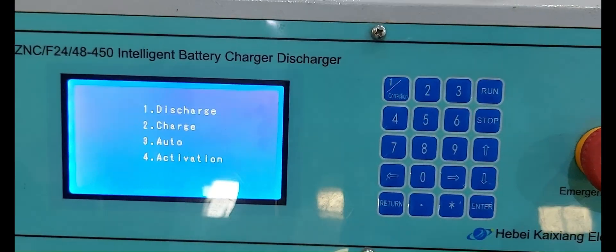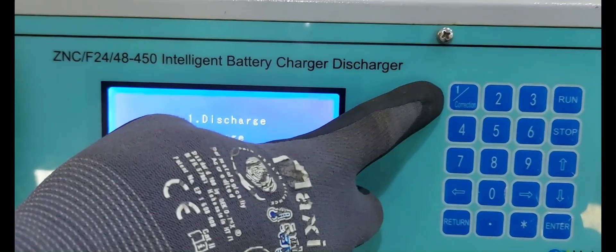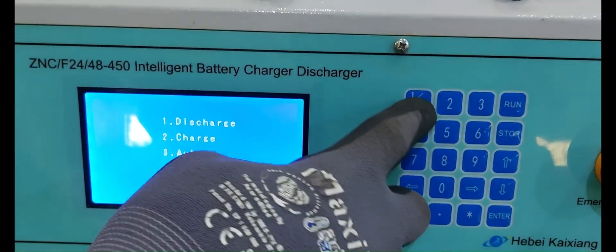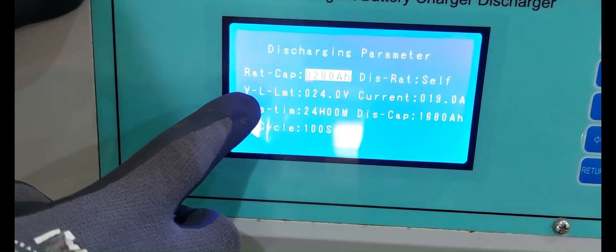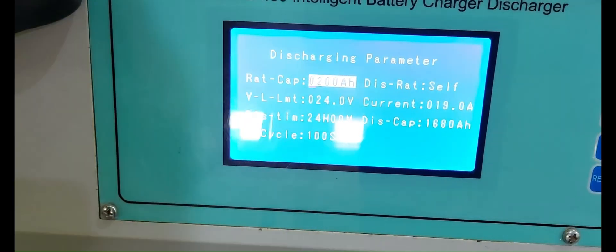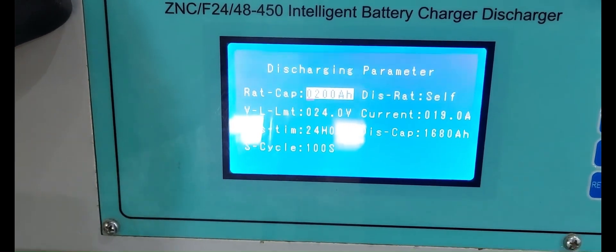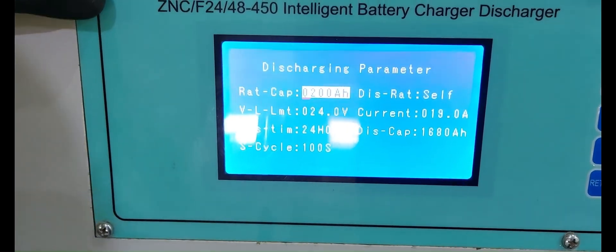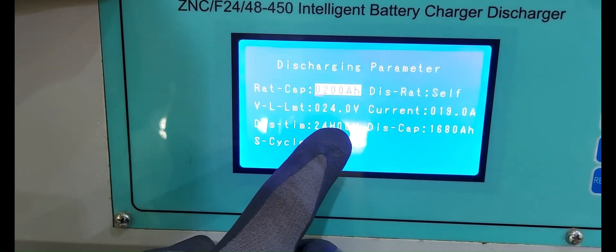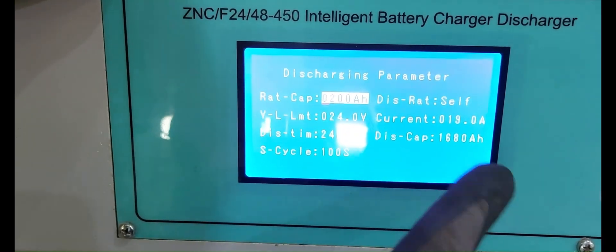Next, we are doing the discharge parameters — the discharge scenario. First, check the discharge capacity — rated capacity of 200 Ah. Discharge ratio: self. Voltage limit low limit: 24 volts. Current: 19 amps. Discharge time: 24 hours. Discharge capacity: 1680 amp-hours. Discharge cycle: 100 seconds.